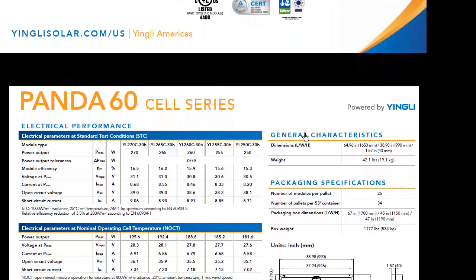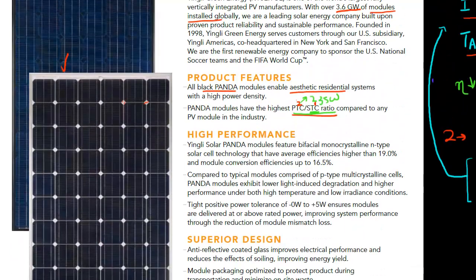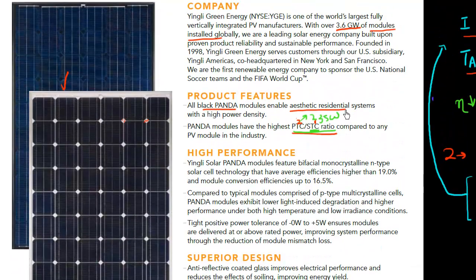So this STC rating is often given in the datasheet itself. So it says that under standard test conditions, the maximum power for this panel is 270 watts. So the PTC to STC ratio is essentially 235 divided by 270. So this is not that shabby. It's close to 90% over here.